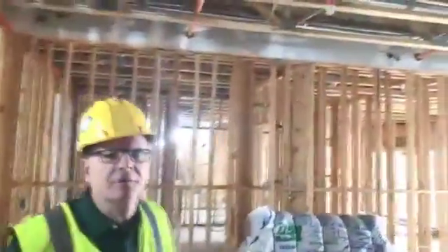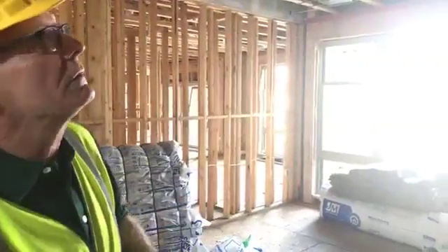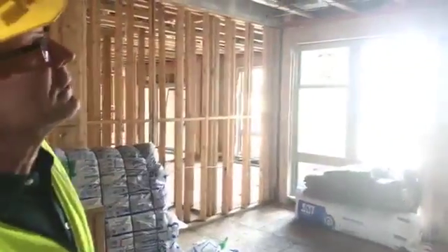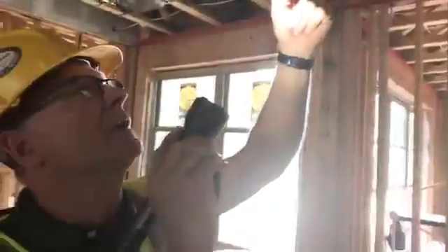We're at unit 208. This is a mirror of the unit 408 we looked at that was drywalled. It's a good unit to show our audience today exactly what's going on with this duct system. As you can see, they've used a combination of materials, duct mastic and foil tape. Again, it's a commercially rated fire code tape they have to use. You're looking at the fire damper that's in the housing and the duct boot that drops down. When we initially did the test, we were having some leakage issues, so they went ahead and sealed it from the outside and inside, and some stuff in the shop prior to the job site.